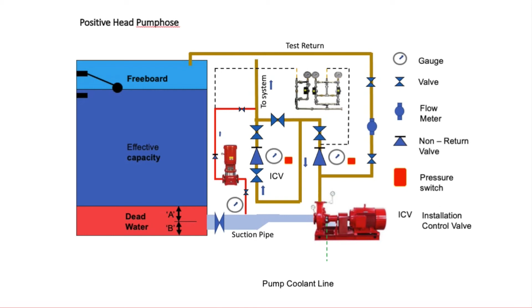systems. Now each type of system is limited to size. Okay, so for one control valve feeding a roof area, it can cover up to an area of 9,000 square metres. One control valve feeding a set of racks can cover 2,000 heads. Installation control valves have a bypass arrangement so that the system can still be live during sprinkler servicing. Okay. Now that's you keeping it live.